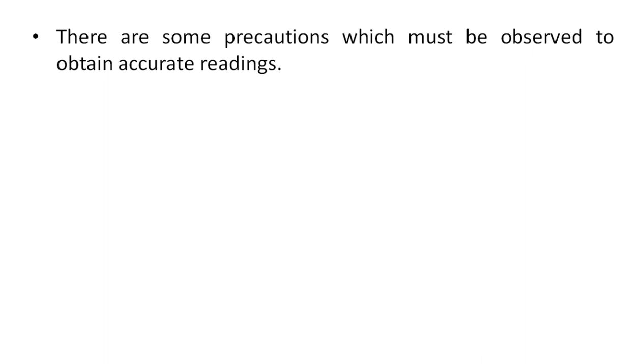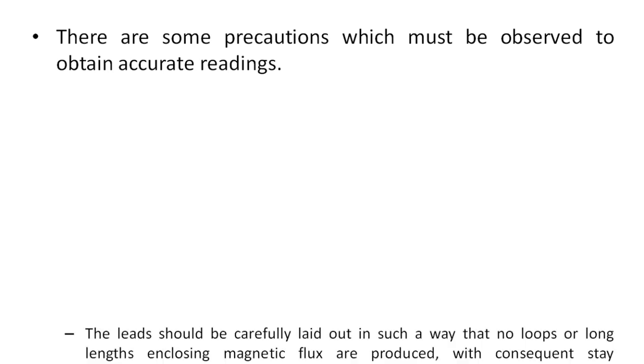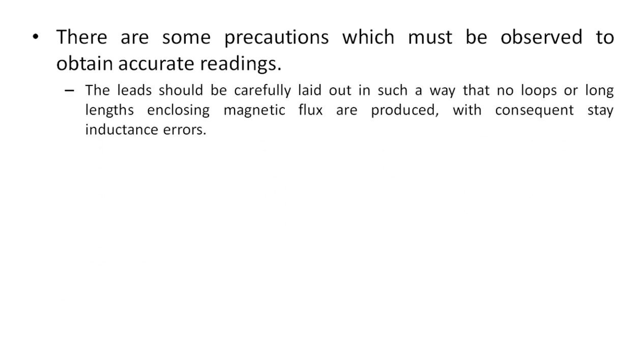Lead capacitance and lead inductance refer to the parasitic effects introduced by the contact leads we connect across a resistance, capacitor, or inductor. These leads provide some inductance and capacitance. That is why there are precautions we must observe to obtain accurate readings. The first precaution: leads should be carefully laid out so that no loops or long lengths are formed, which would enclose magnetic flux and produce stray inductance errors.